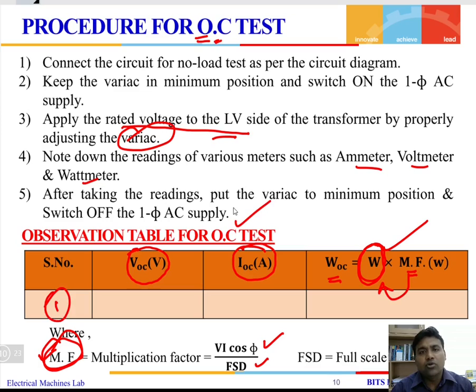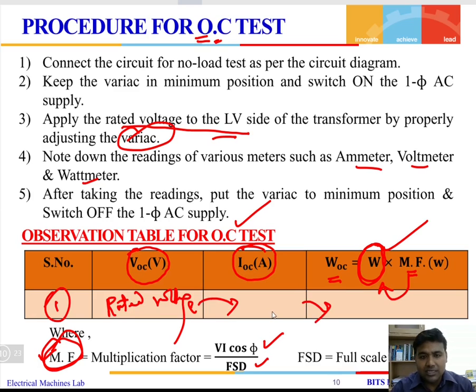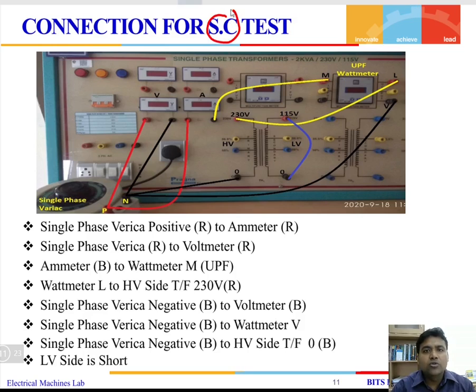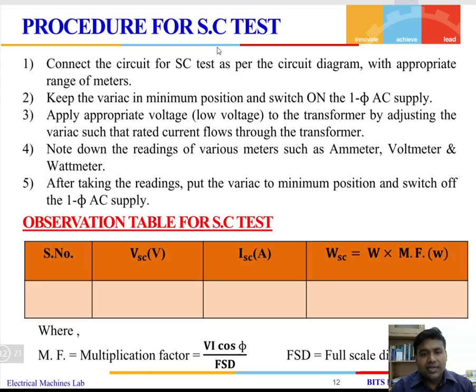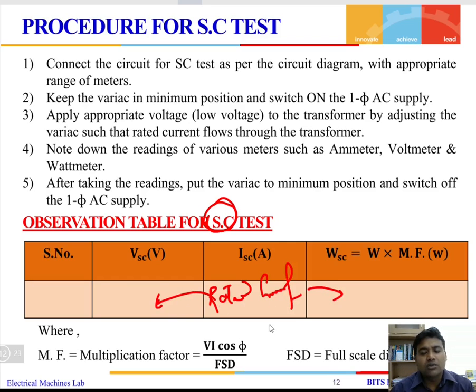A single reading is obtained for the OC test, and the OC test is done at the rated voltage. Corresponding to the rated voltage, you record the current and the power. For the short circuit test, you short circuit the low voltage side and all measuring instruments are connected on the high voltage side. Using the variac, vary the voltage slowly so that the rated current flows in the device — the SC test is done at rated current. Measure the corresponding voltage and power.